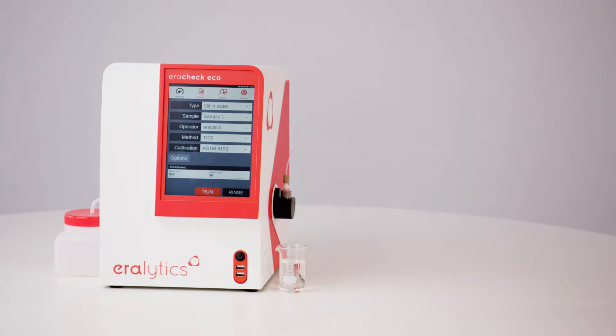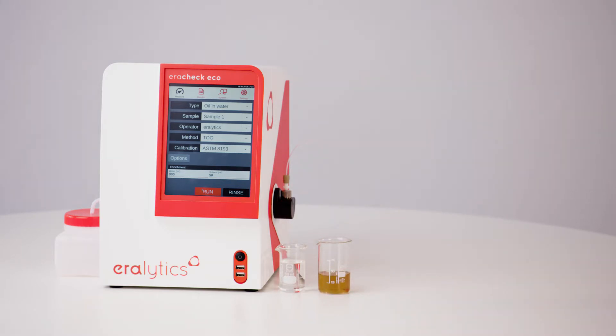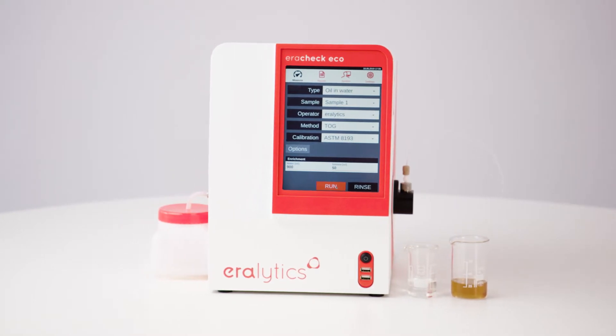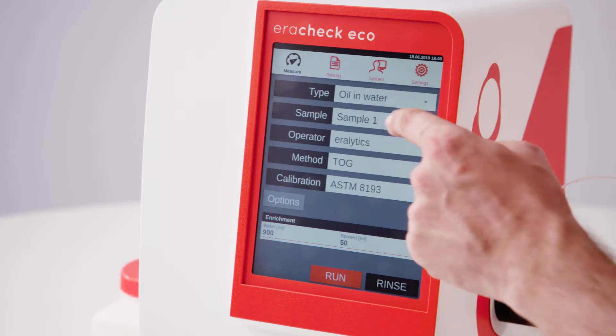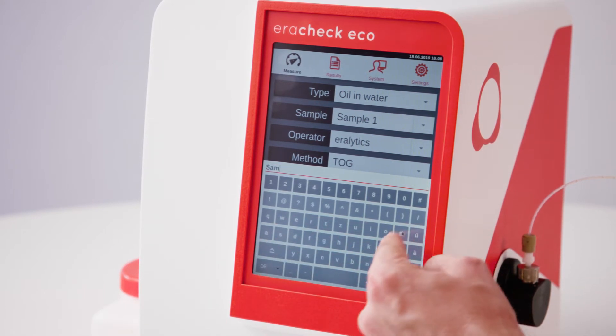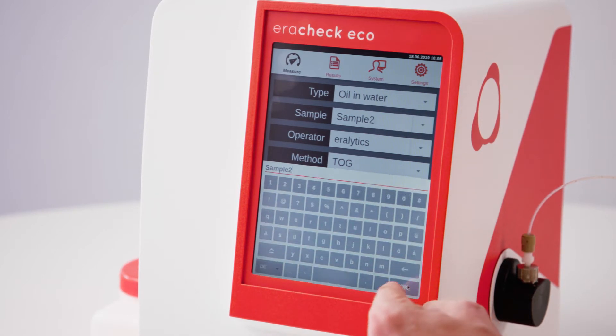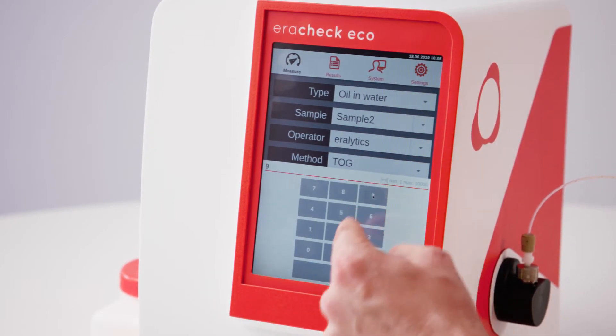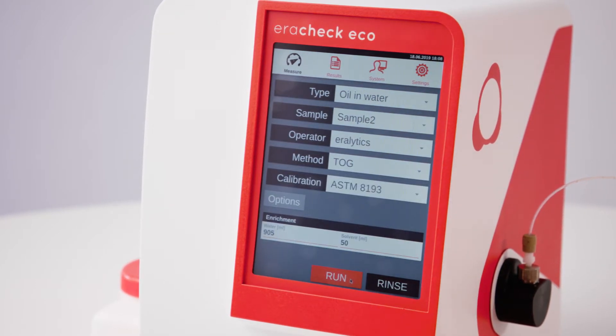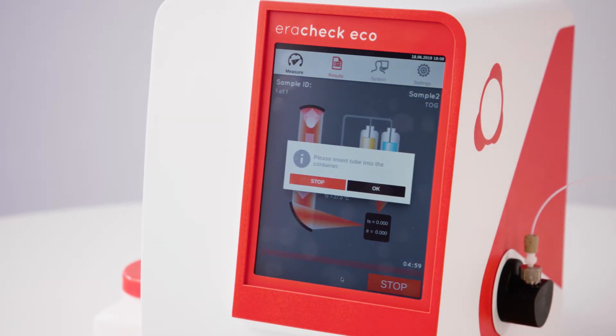The extracted sample is ready for automatic analysis by eraCheck. The intuitive user interface guides you through the measurement. Enter a sample ID, operator, and enrichment factor. If required, adjust the method or select a user-generated calibration. Press Run to start the fully automated measurement.